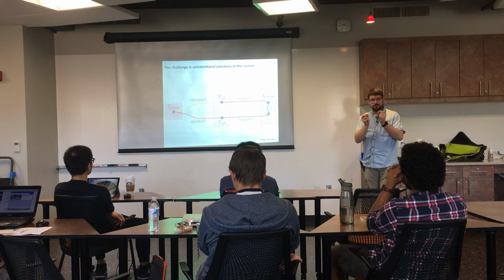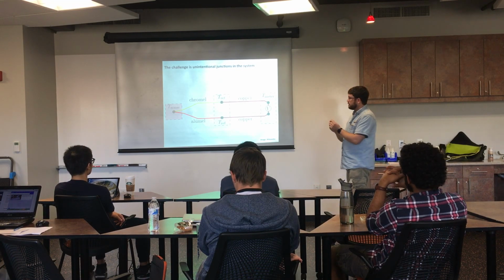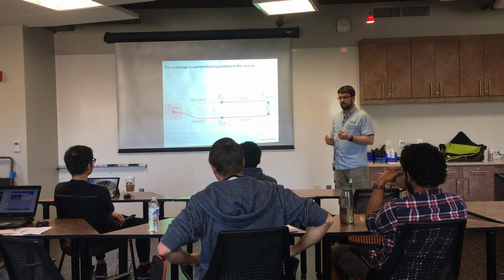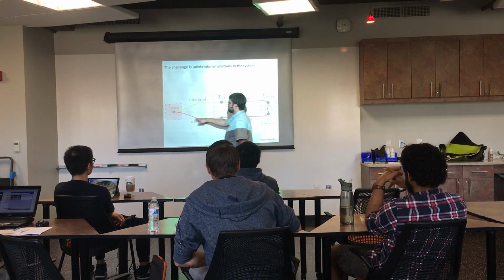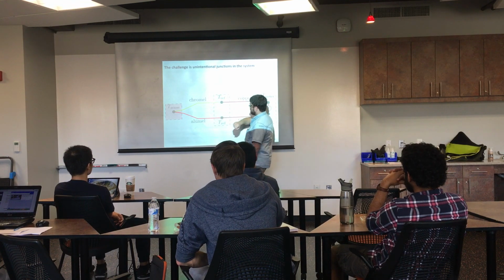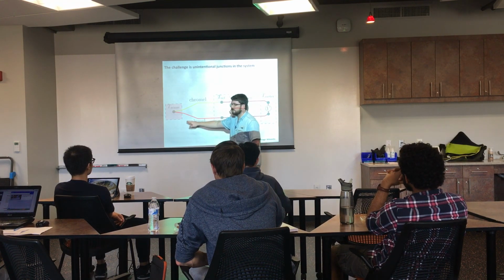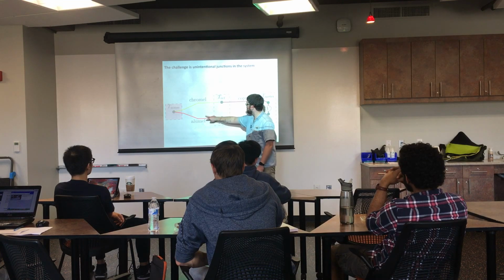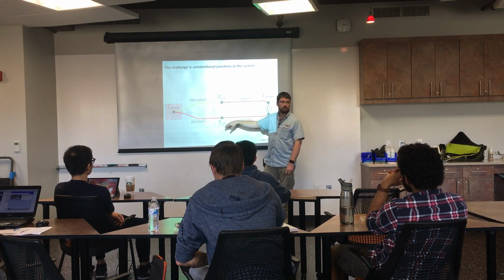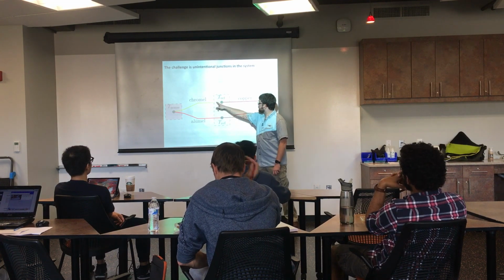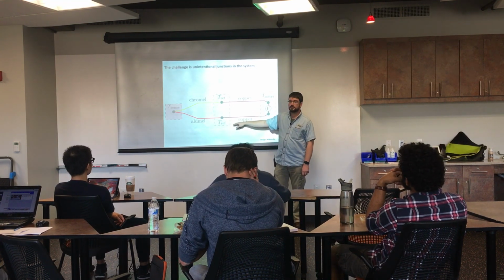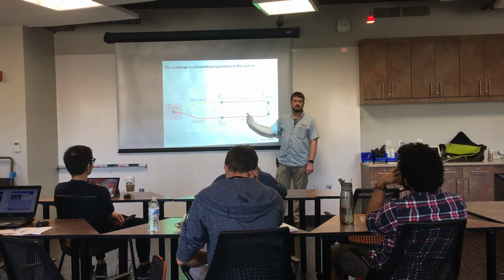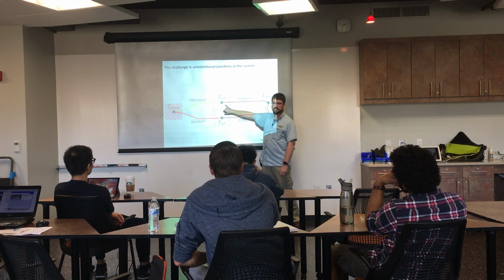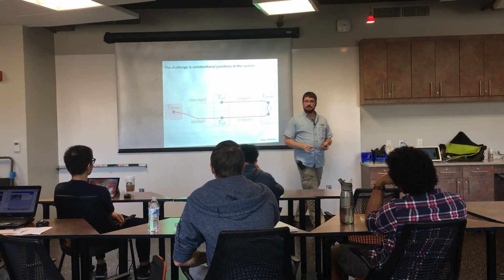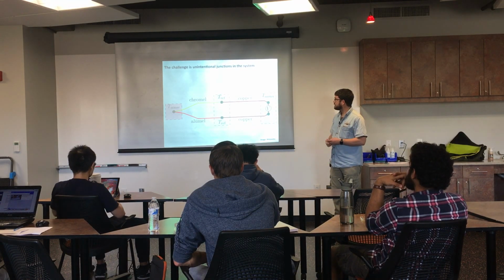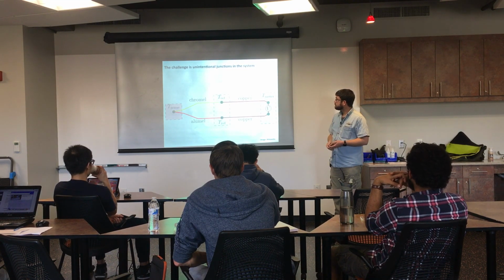But the challenge is, remember, any two kinds of metal that we have joined together are going to be a thermocouple. So let's say out here, you have your thermocouple on your experiment, and this would be a type K. So we've got chromel and alumel alloys, the wires running back. And then we're going to connect it to the computer or to our multimeter, whatever. Well, now we have a chromel copper and an alumel copper junction. So now this circuit has 3 thermocouples in it. And these two are going to change with the room temperature. So that's not an ideal thing, right? We want to be able to correct that out. And there is a way to do that.